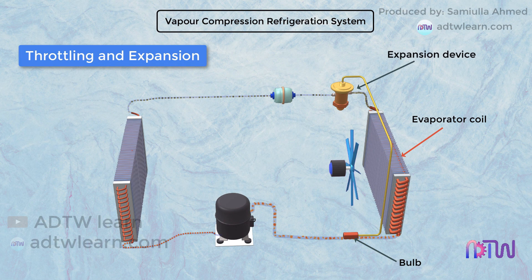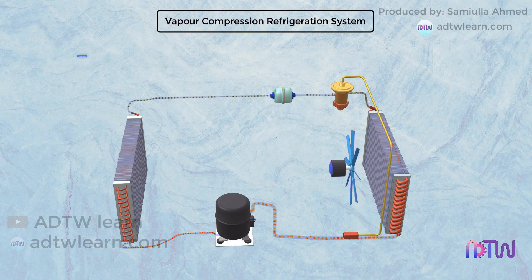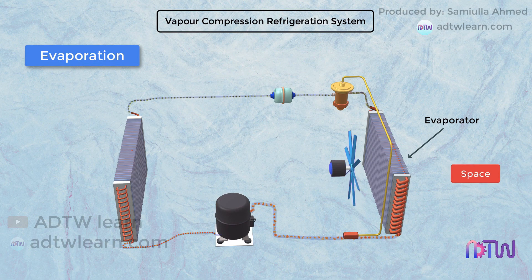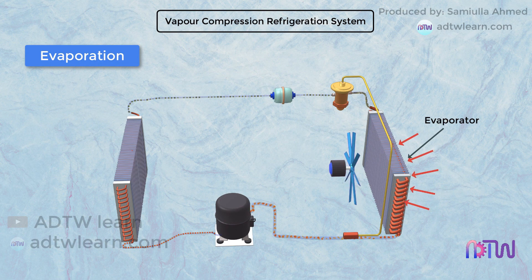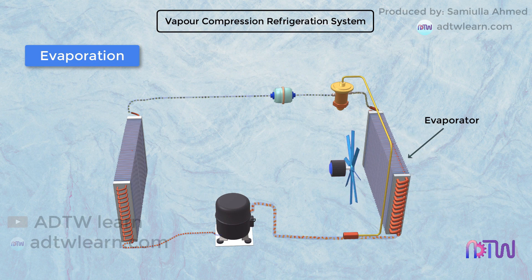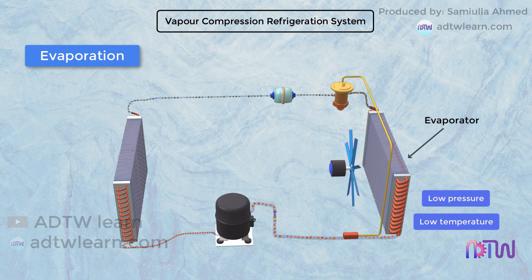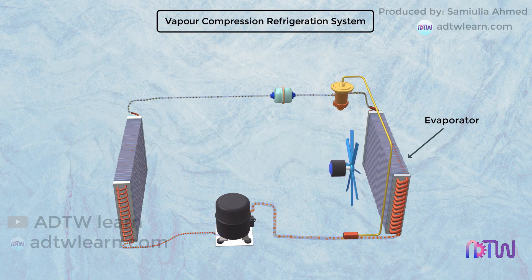The refrigerant entering the evaporator is at a lower temperature than the space to be cooled. Therefore, it evaporates and absorbs heat from the closed chamber inside which the evaporator coil is placed. Heat extraction from the space happens at low pressure and temperature. The compressor suction effect helps in maintaining the low pressure at the evaporator side. This step is called isobaric heat extraction.